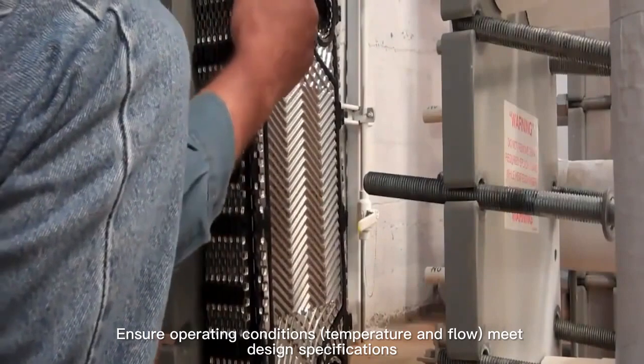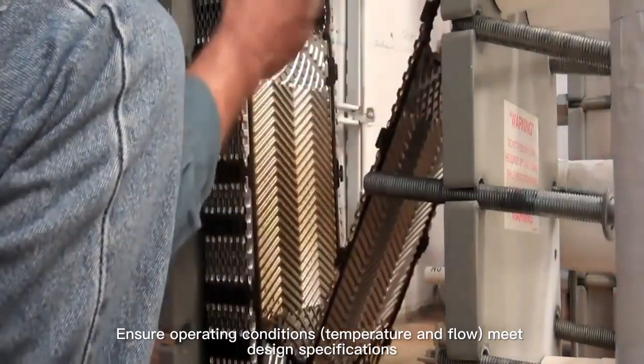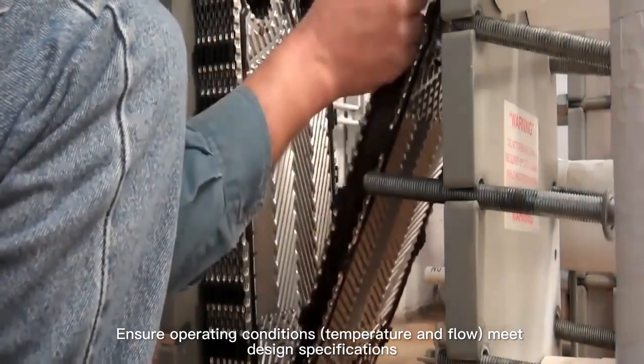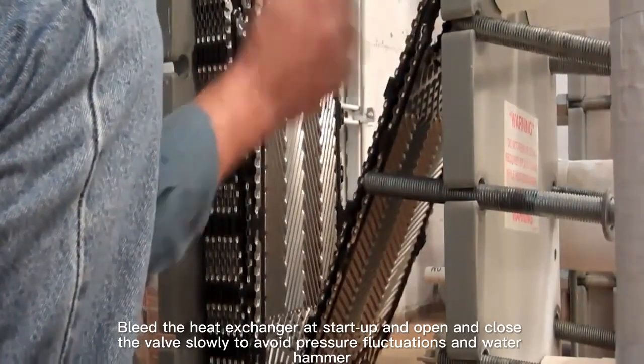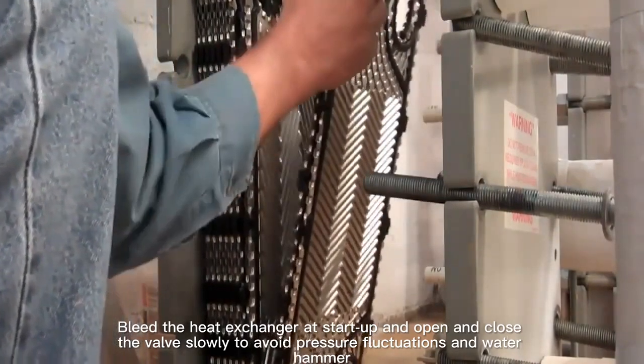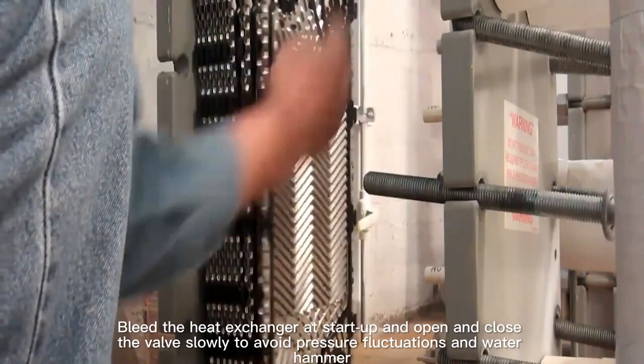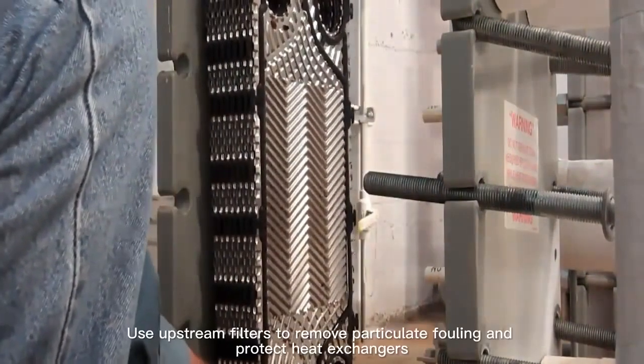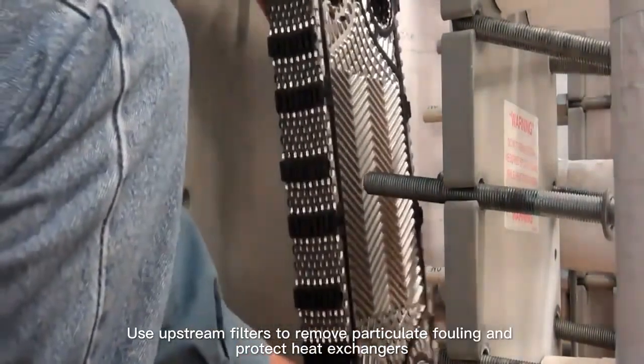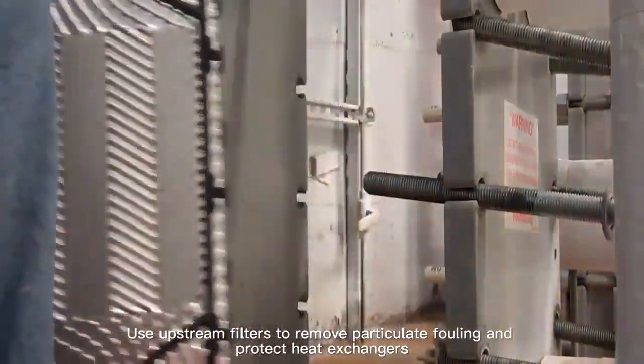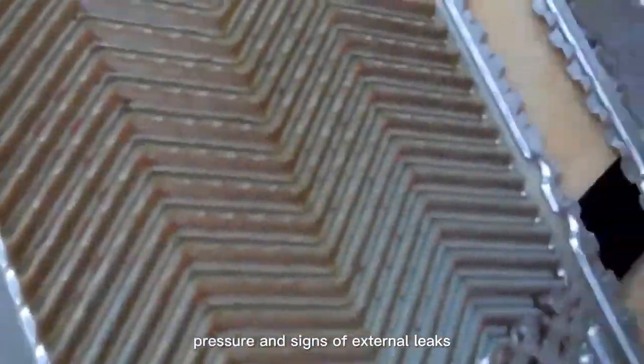Ensure operating conditions, temperature and flow, meet design specifications. Bleed the heat exchanger at startup, and open and close the valve slowly to avoid pressure fluctuations and water hammer. Use upstream filters to remove particulate fouling and protect heat exchangers. Check daily for all changes in temperature, pressure, and signs of external leaks.